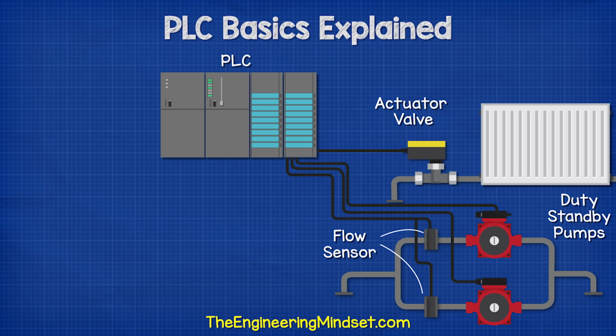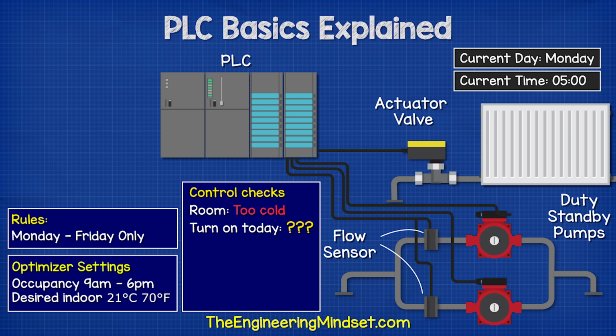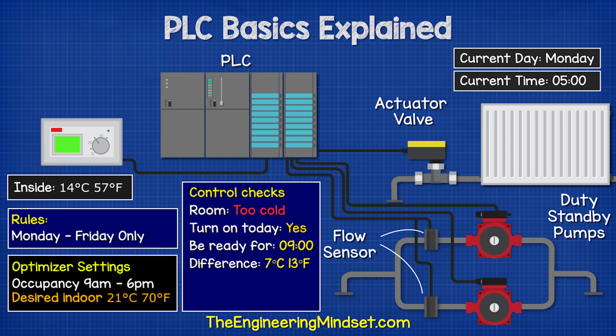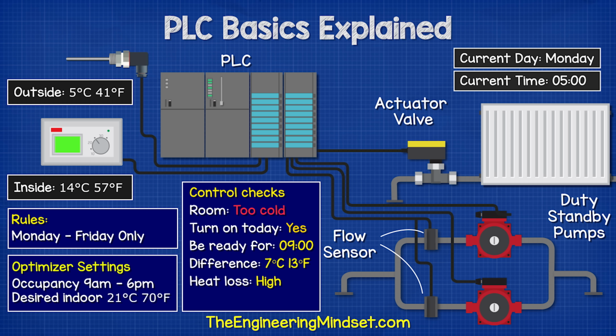However, before the heating system and pump start, the PLC will check with the clock, should the heating turn on today, and if so, at what time will the building be occupied? The clock says yes, the scheduled occupancy time is 9 a.m. The PLC then checks the current temperature of the room and calculates the difference between this and the desired temperature. It then checks the outdoor temperature to calculate how long it will take to heat the building, because on a very cold day, there will be a greater heat loss, and so this will take longer. From this, the PLC calculates what time it needs to turn the heating system on so that the building is at the desired temperature ready for 9 a.m.